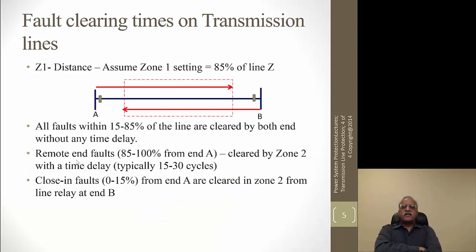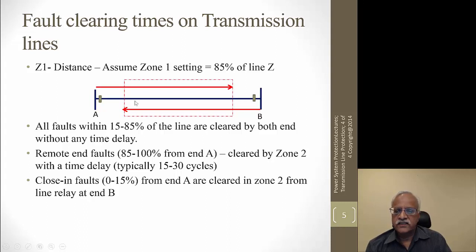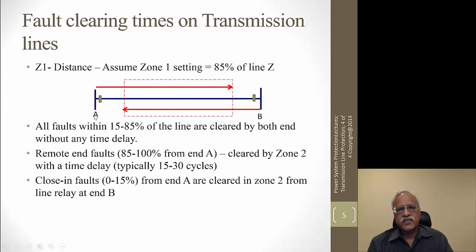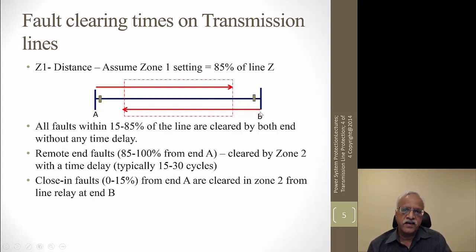Now looking at the transmission line: if there is a fault from 15% to 85% of the line section, assuming the zone 1 distance relay is set to 85% of the line, the relay at A looking towards B operates instantaneously if the fault is within 85% of the line section. Similarly, the relay at B looking towards A operates without any time delay if the fault is within 85% of the line section. So for faults from 15% to 85%, both relays see the fault and clear it instantaneously.